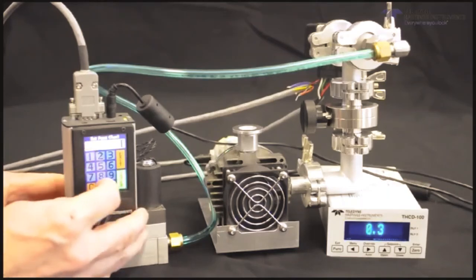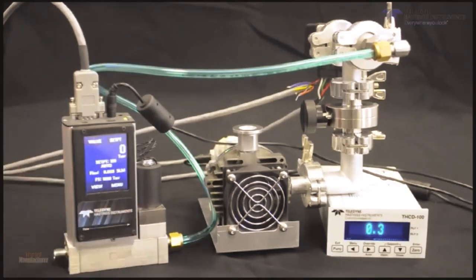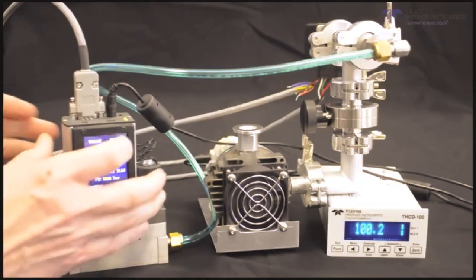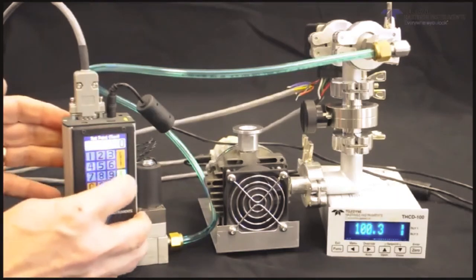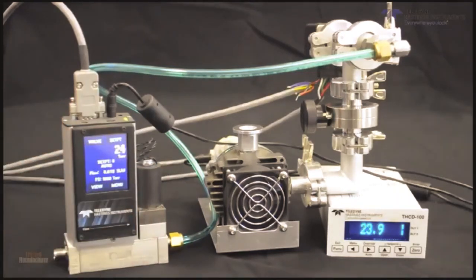Now we are ready to enter a pressure as the command signal. We'll use 100 torr. If I were doing this with one of our analog power supplies, I would need to ensure that we would be in the analog command mode, as I demonstrated earlier. For this demonstration, I'm using a slightly modified version of the digital 300 firmware, which allows the user to see the pressure and enter a pressure set point as command. So I'm using the digital command mode. Now, we will set it back to 0 torr.